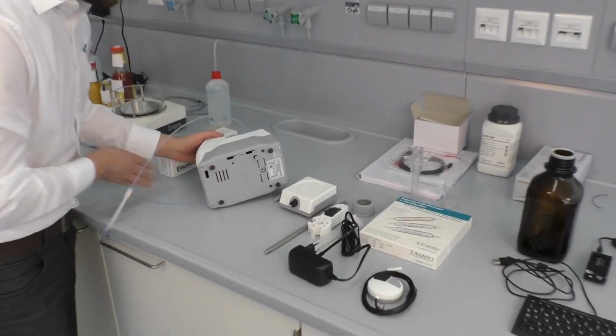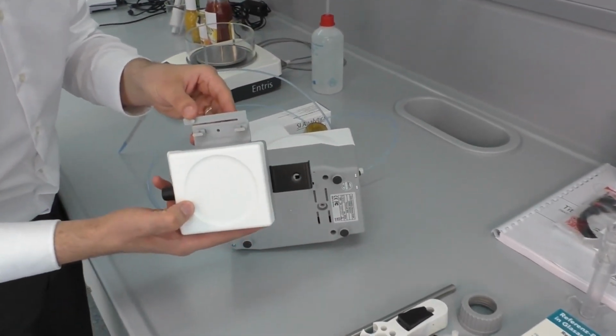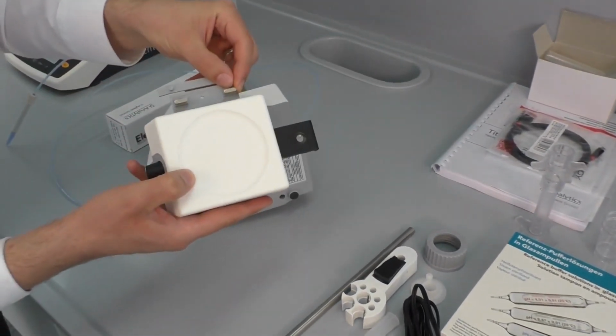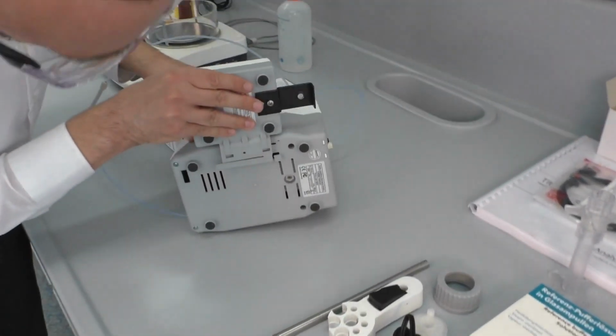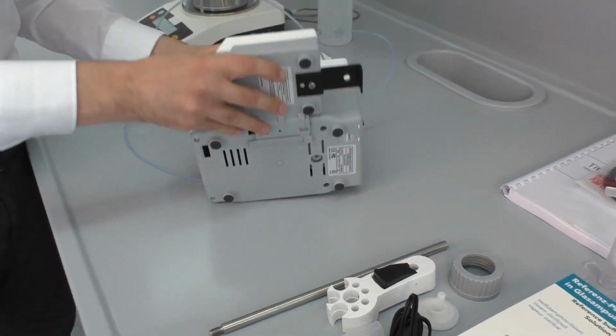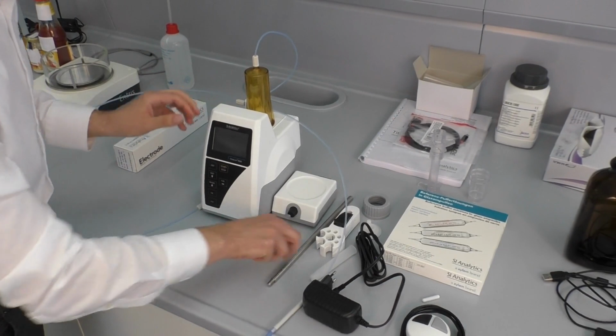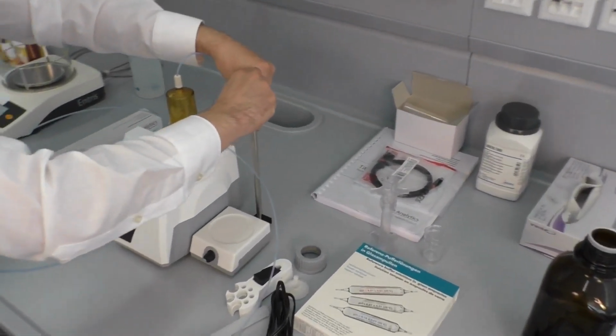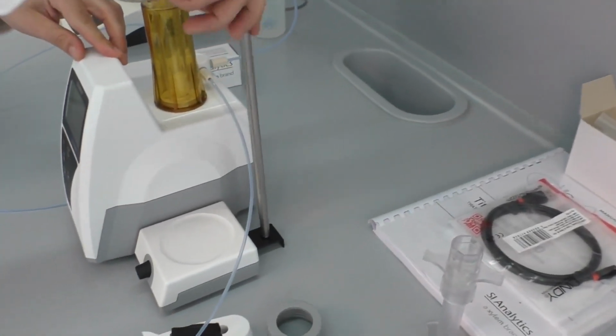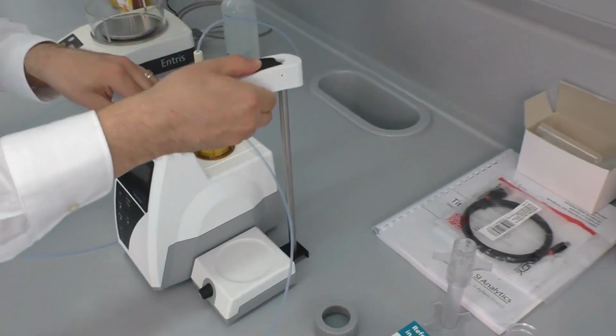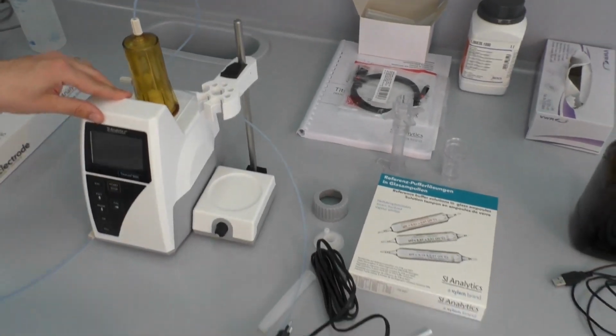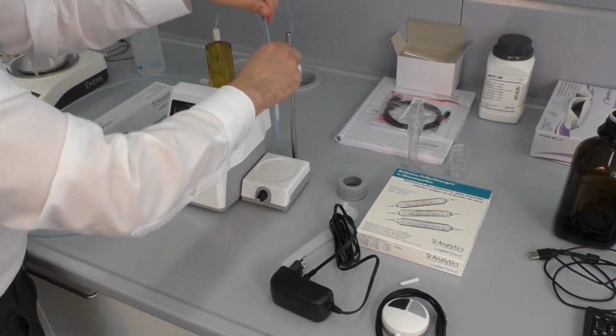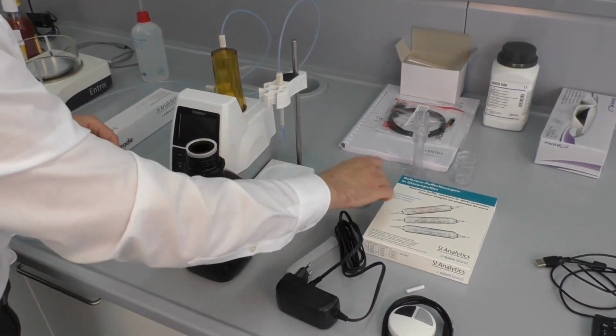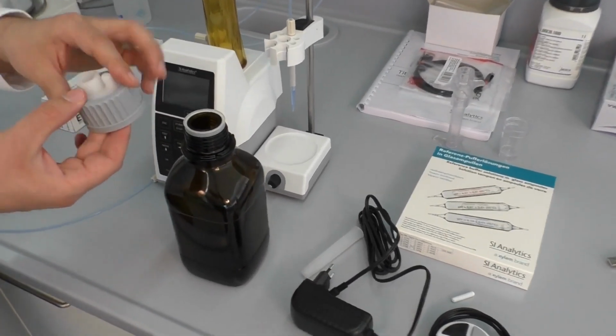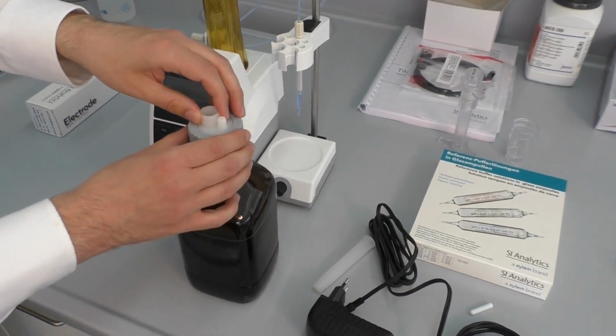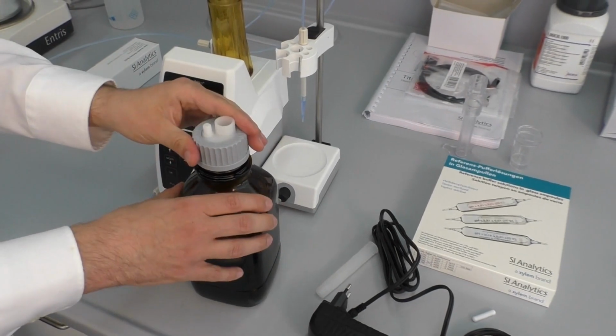The first thing to attach is the magnetic stirrer. The magnetic stirrer is run directly by the instrument via these gold contacts. Now we can attach the stand rod together with the titration clamp. The titration tip is attached. We can mount the adapter for the reagent bottle, which is not part of delivery and is an optional accessory.